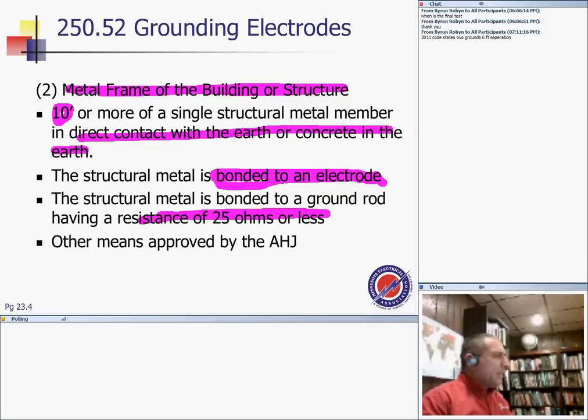So that's open to the interpretation of the authority having jurisdiction. Anything else about this? For the most part, especially in 2011, guys, if you have the steel frame of the building, the beams in direct contact for 10 feet with foundation or without foundation, you create a ground electrode system.